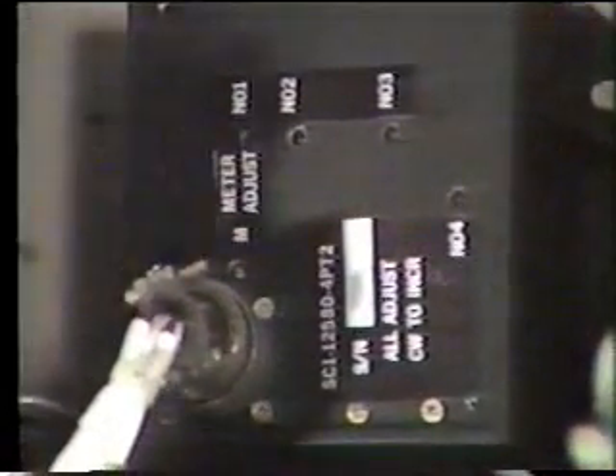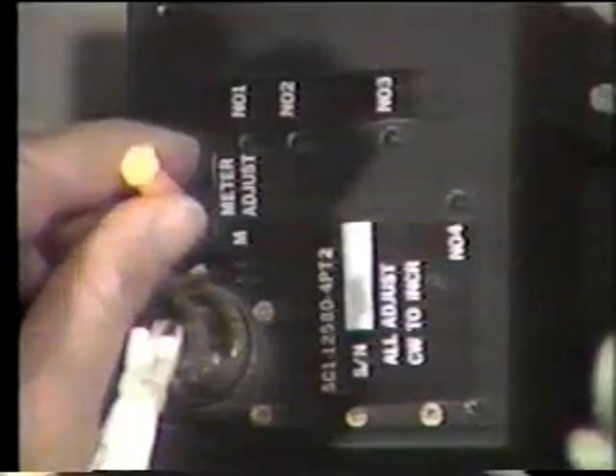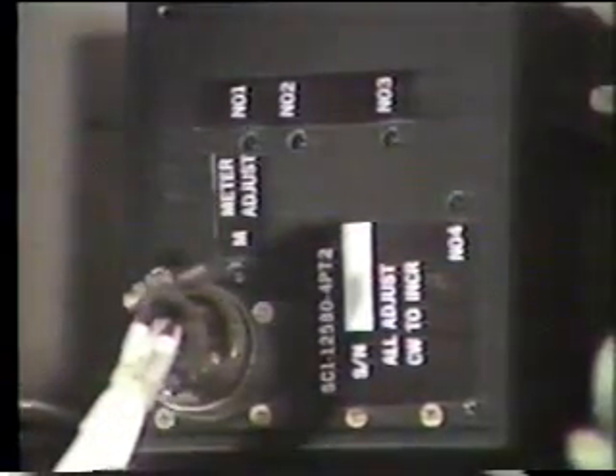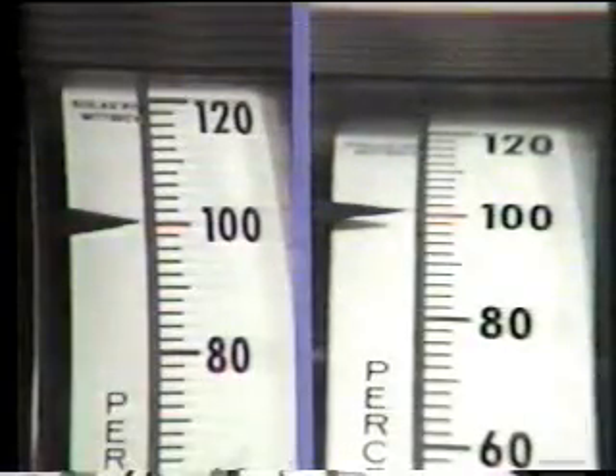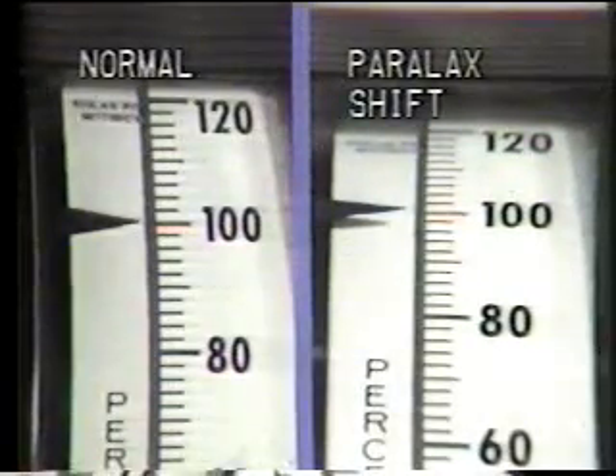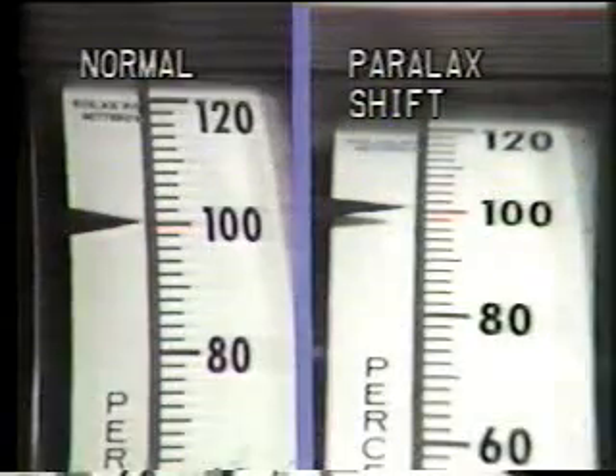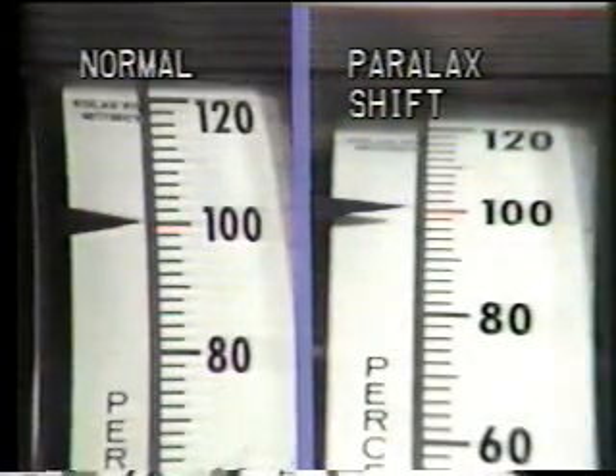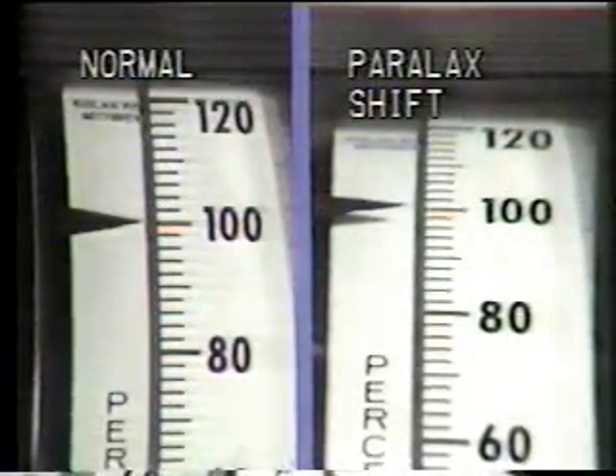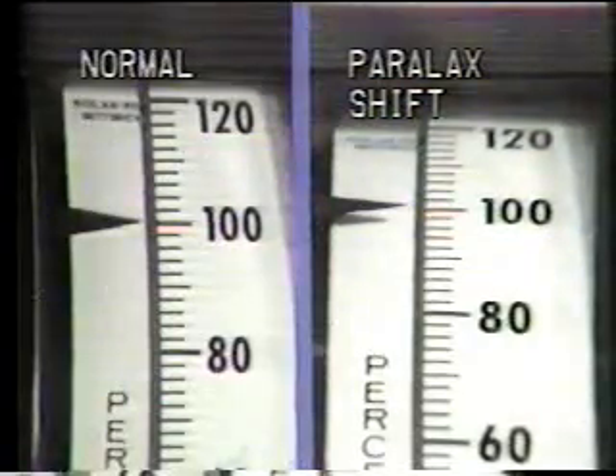If it doesn't, adjust the M, or meter adjust, on the speed control unit. Note, avoid parallax when reading the meter during this adjustment. Be sure to look at both the needle surface and the scale surface from a 90-degree plane of vision to obtain a correct meter reading.